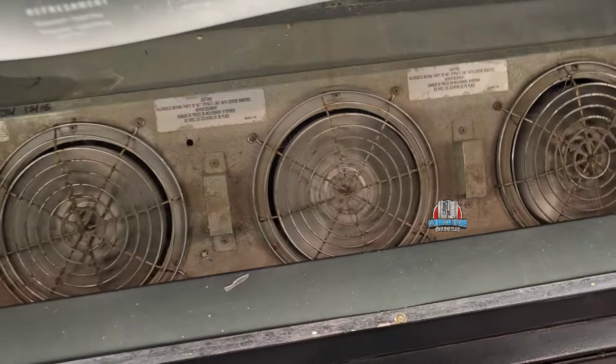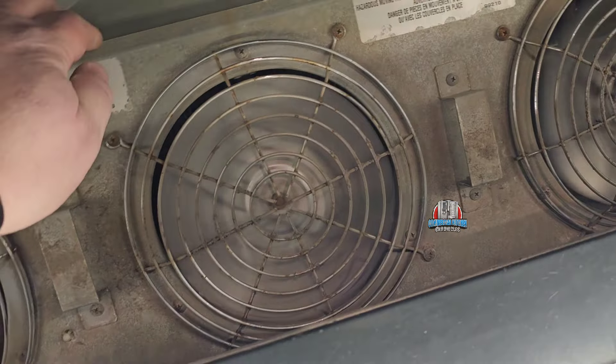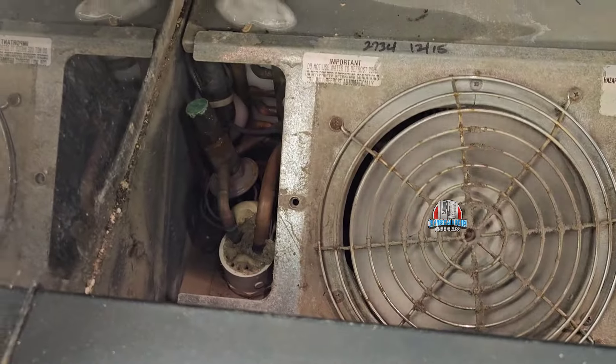Checked the coil — it's not frozen up. It's got some ice right past the TXV, a little bit over there. I'll get it cleaned up. Luckily I don't have to pull the whole thing out. Let me pull this out and show where the leak is.